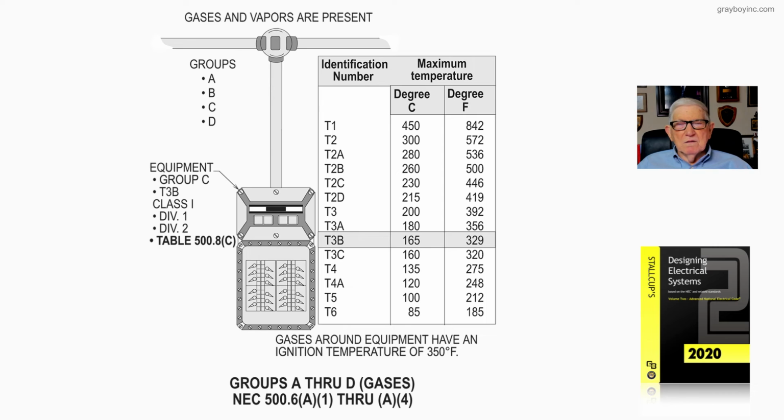So that's what you must do. You have to find out, based upon the gas or vapor, what the ignition temperature of that gas or vapor would be, and you'd find that in table 4.4.2 of NFPA 497, and then you would classify the area based upon the vapor being there all the time, or it could only escape due to a malfunction of some fitting, or say a bleed off valve, a check valve, some of those similar type valves. And that's what this illustration 21-6 is illustrating to the designer or user of the NEC.